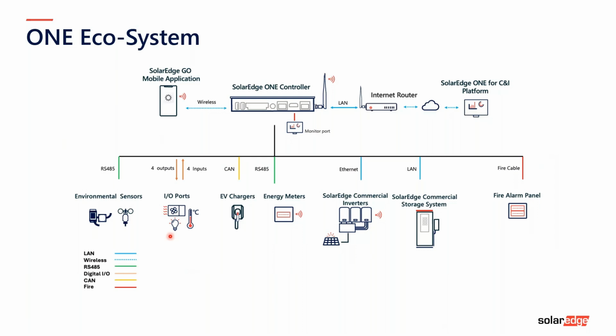Next, you've got your commercial EV chargers. These can be monitored by the One Controller, and you have a selection of energy meters. Currently we support the SolarEdge energy meter, the K2. We also support the Innopro P380, I believe, and we're finishing that one off now. The beauty of the One Controller is that it also provides G100 for any meter attached to it. So the system provides G100 for the entire system, including the meter. You can have an Innopro meter with G100 features supported by a One Controller, which wouldn't be the case if you just connected it to a normal inverter.